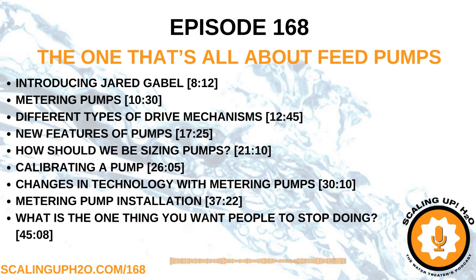If you look at a centrifugal pump versus a diaphragm pump or a dosing pump, the curve is much different. I always kind of laugh when somebody asks me for the dosing pump curve because I'm like, well, that's really not going to tell you a whole lot of information. It's just a square on the screen. So we're not trying to meet a duty point with a fluctuating pressure. It's just the pump can always pump against whatever that maximum pressure is, regardless of the feed rate or the flow rate. So I always start there. And then it's a matter of a question on compatibility, like we just talked about.